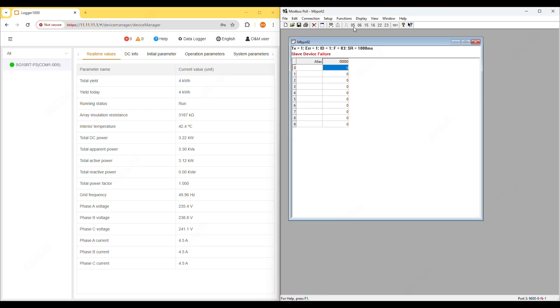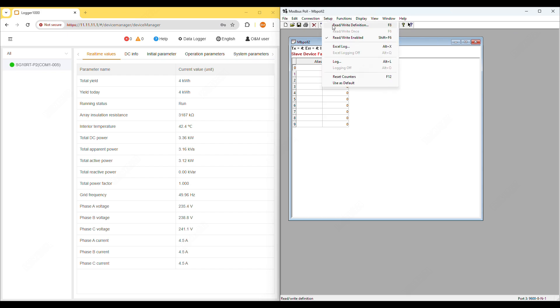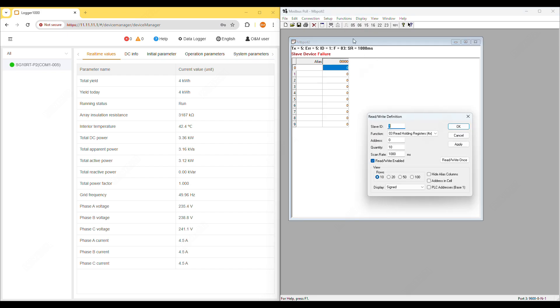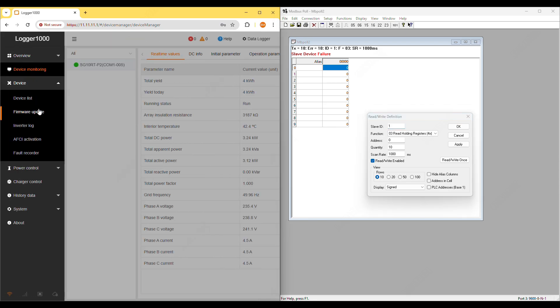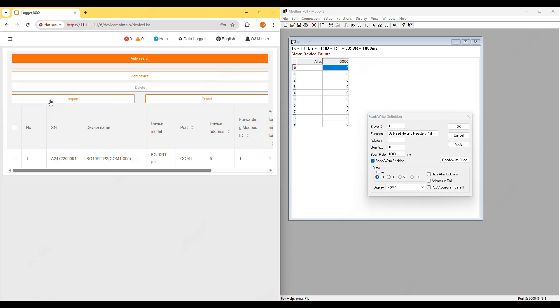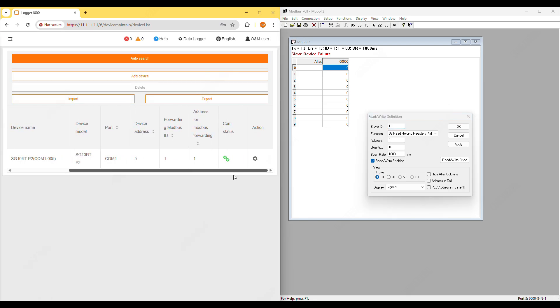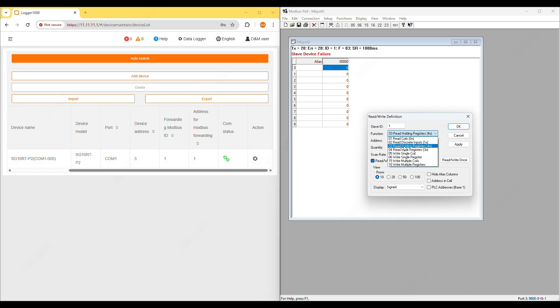Next, go to setup, read-write definition. For slave ID enter 1. You can verify this in the logger under address for Modbus forwarding. For function select 04 read input registers 3x.